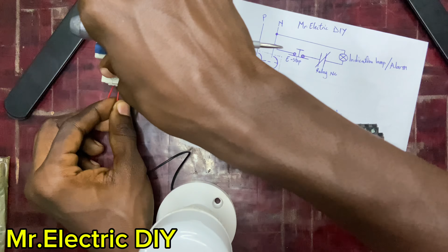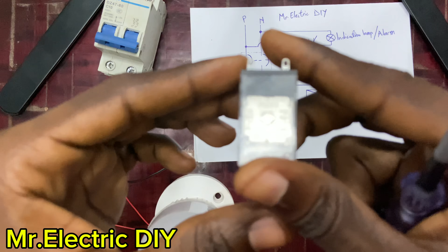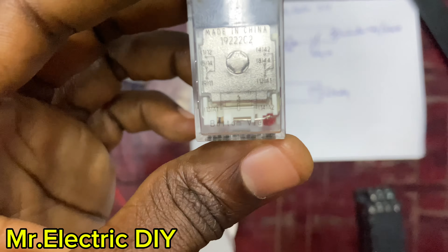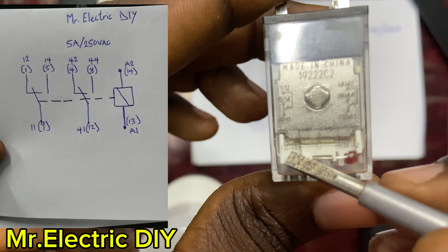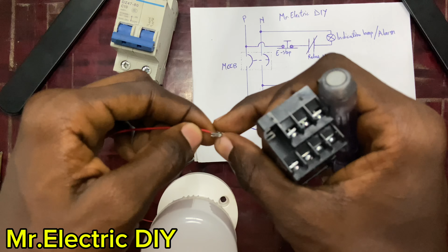So we use these cables. This is my live. On the relay, 13 is the live and 14 is the neutral. I have it written here. Over here you could see that we have 13 at this side. This is 13. That's the A1 and 14. That's the A2. So I'll connect my live to the A1 and the neutral to the A2. And A1 is number 13 and A2 is number 14. The live from the breaker to number 13 on the relay socket. I have 13 here. Just insert it. This black cable here is the neutral. That is number 14.